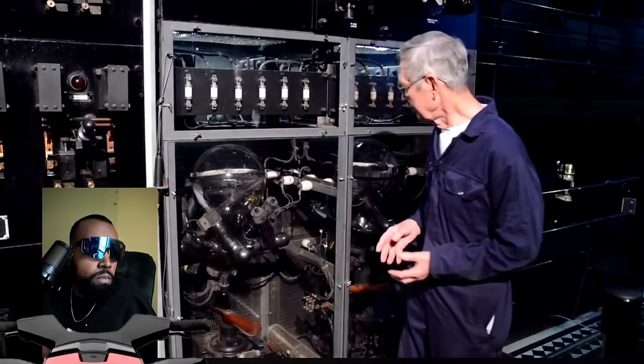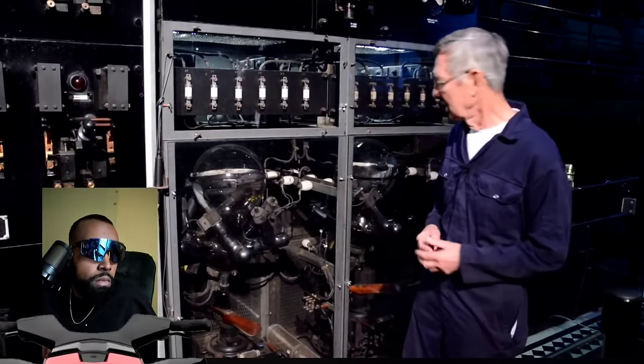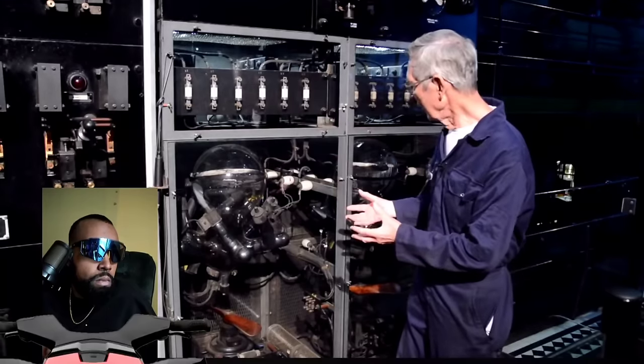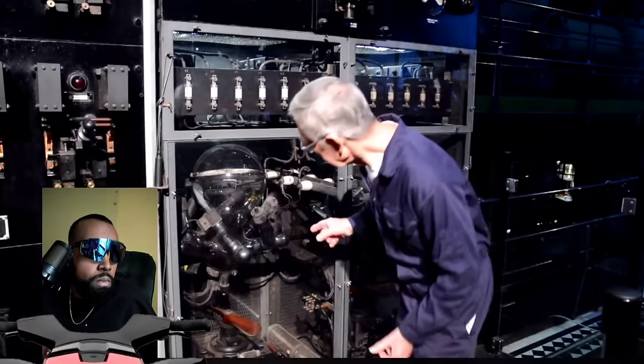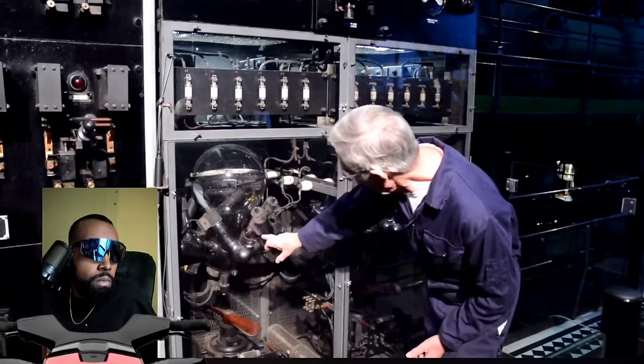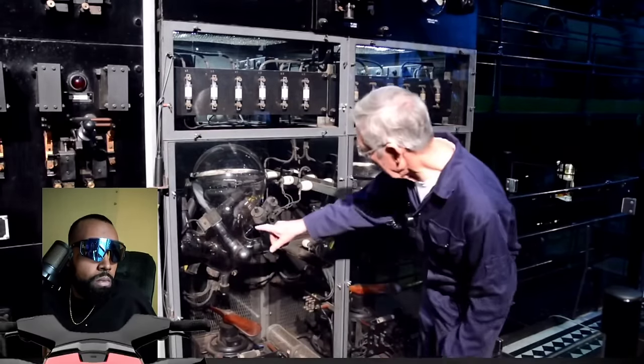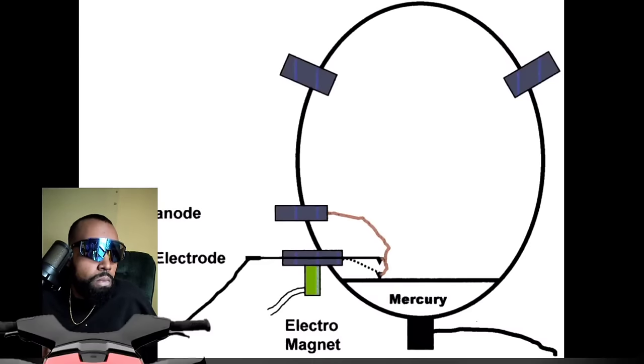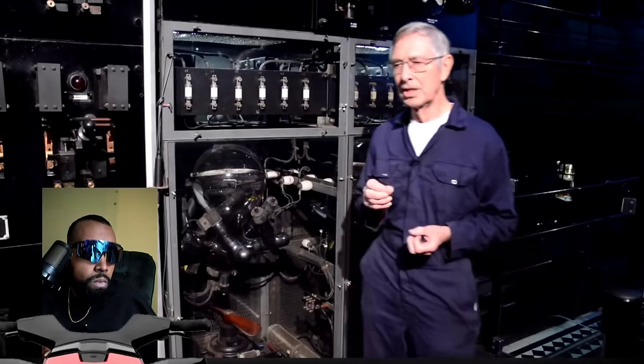Now, to start a rectifier, you need an arc. As it's a totally enclosed glass envelope, what you have is a spring wire from a small arm, just out of sight, which has an electromagnet under it. When we start the rectifier, the electromagnet pulls the wire into the mercury pool. That shorts the electromagnet out, which releases the wire and creates a spark, which is then picked up by two small anodes at the back to keep the arc flowing. What happens is when the spark is created, it ionizes the mercury vapor and makes it conductive.